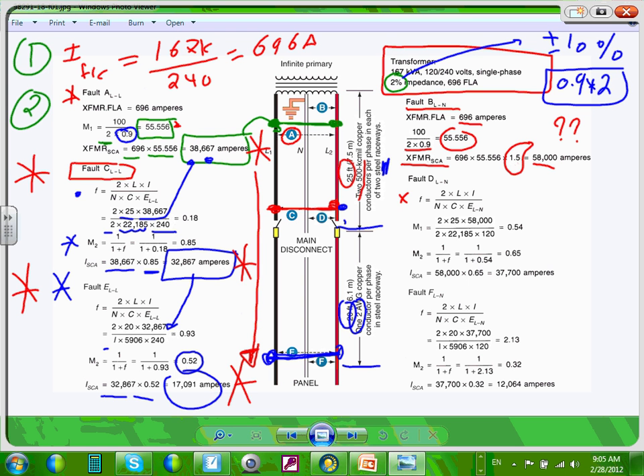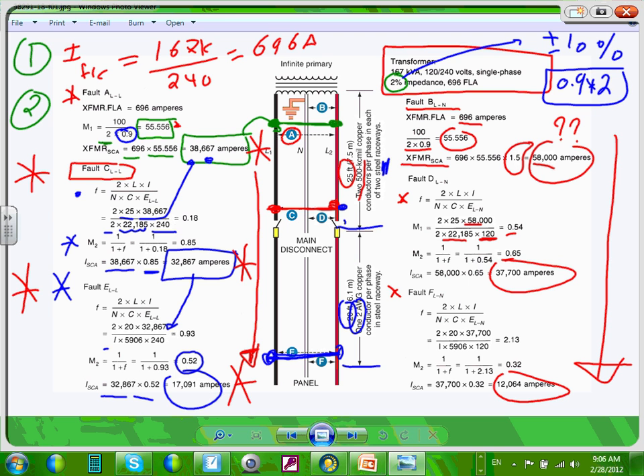Then you plug it into this formula. The same thing, 2L, I, and C, E line to neutral. The only difference is we're using line to neutral voltage here, so a different voltage. The same conductor. Here's my multiplier. Then at point D, I have 37. You go down to point F, same thing. You plug in your numbers, and at point F, I have 12. The same thing, guys, you can see the ground fault is going what? Going down. The ground fault is going down as you move away from the transformer.